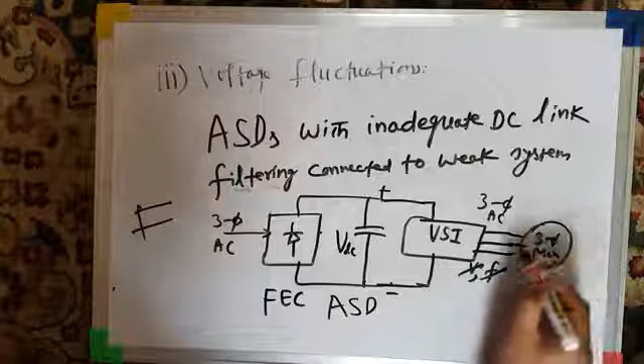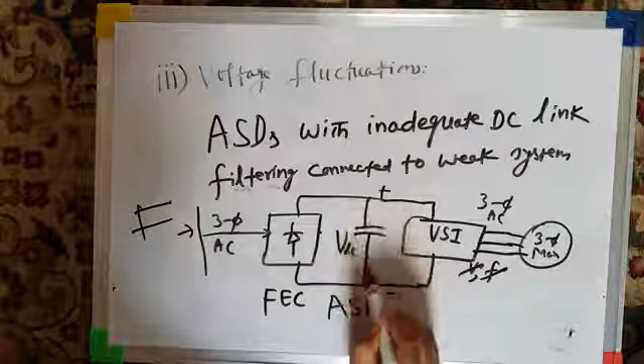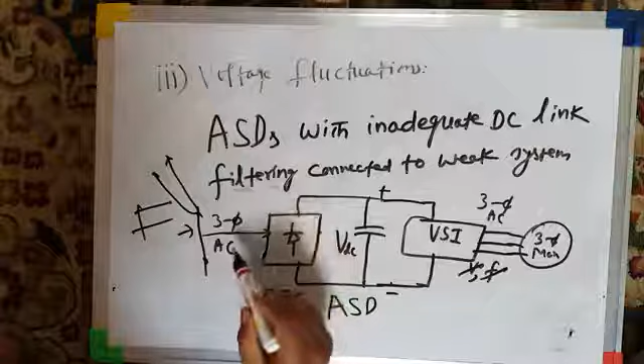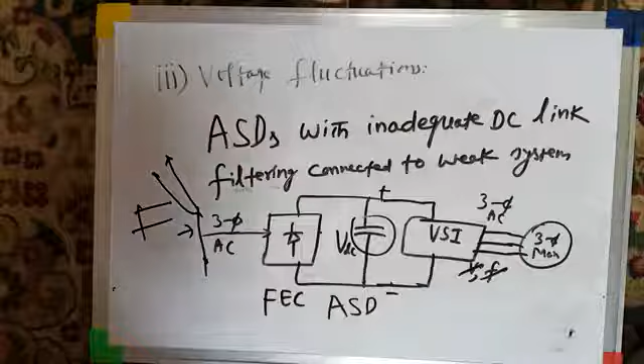Now, if this DC link filtering is not adequate, if this filter capacitor is of a lower value, and your system is connected to this three-phase AC supply, which comes from a bus, and if this bus is a weak electric system, then this inadequate DC link filtering also results in voltage variations at the bus here. And since this bus does not feed your ASD only, it feeds other consumers also, other consumers will observe voltage fluctuations. So adjustable speed drives with inadequate DC link filtering connected to weak AC electric systems are also responsible for voltage fluctuations. Voltage fluctuations, of course, are rapid variations in the voltage, and they are a cause of concern. They are a power quality problem. Okay, so that was point number 3.